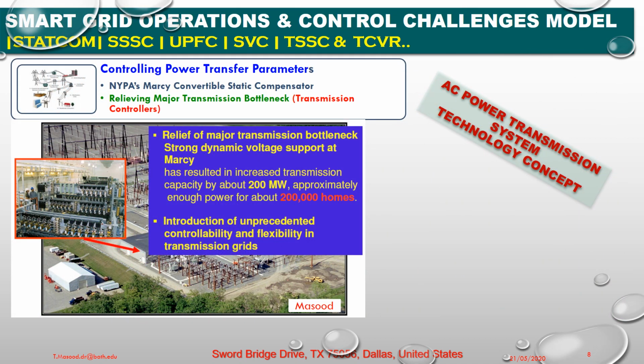As I've discussed in my earlier lecture number 9, a New York case study, massive convertible static compensators, STATCOM, we have. And this picture is dedicated to Dr. Abdullah. So if we can see here, this is STATCOM convertible implemented, relieving major transmission bottlenecks, strong dynamic voltage support at Marcy. So to increase the transmission capacity by 200 megawatt, the 200 megawatt is sufficient for 200,000 homes. So we have introduced controllability and flexibility in transmission grid blocks by implementing STATCOM.